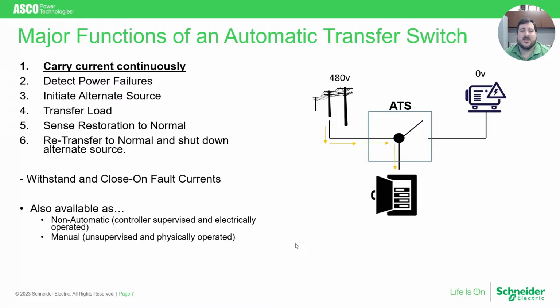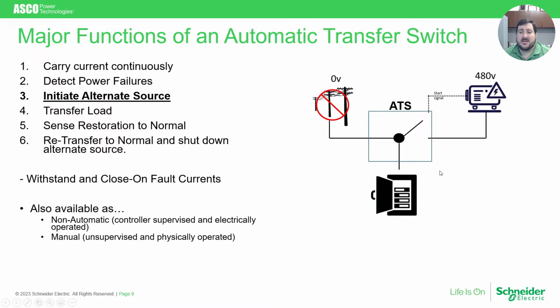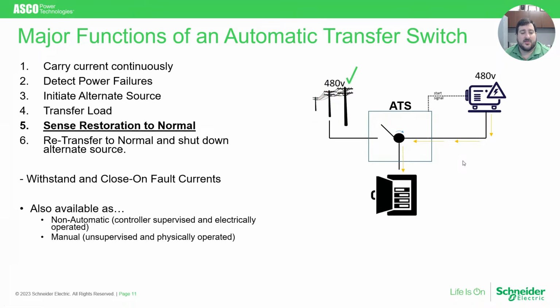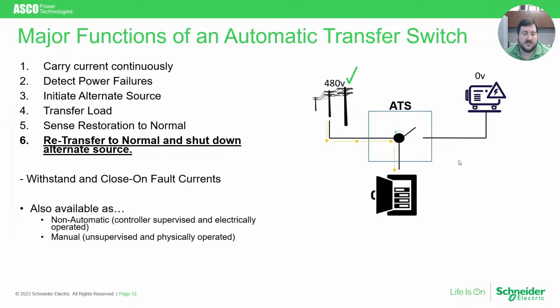So a transfer switch is, in most cases, continuously carrying current while connected to the utility load as a passive device. So 99% of the time, not much is happening on the system. Power is flowing from your utility source down to your transfer switch while the source is good. However, if power were to fail, the transfer switch's job is to detect that power failure, send a control signal to an alternate source of power initiating it, usually a generator type source, that will start the generator to be able to provide emergency power and safely transfer the load to that emergency power source, reestablishing a continuous power supply to that load. It will operate in this mode until it senses the restoration of normal power in the utility power source. And when it senses that, it will then determine it is safe to retransfer back to the source, and shut down the generator safely and effectively.